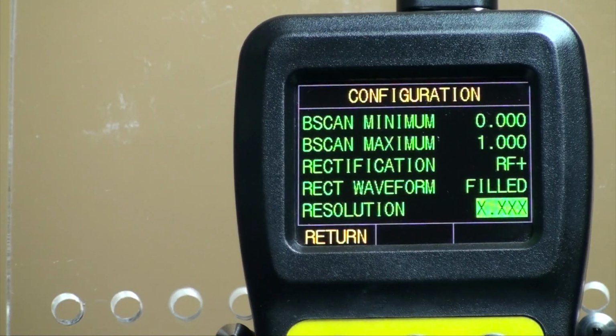Open the menu, scroll down to resolution, and press the P1 button to enter this parameter. Using the arrow buttons, scroll down to the desired resolution, which can be in inch or metric, depending upon the setting that you have already pre-done. The metric units can be set at 0.1 millimeter or 0.01 millimeter, while the inch settings can be set at 0.01 inches or 0.001 inches, respectively.